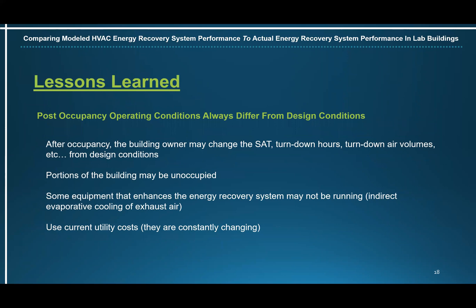Post-occupancy operating conditions always differ from design conditions. After occupancy, the building owner may change the supply air temperature, turn-down hours, turn-down air volumes, etc. from design conditions. Portions of the building may be unoccupied. Some equipment that enhances the energy recovery system may not be running — for example, indirect evaporative cooling in the exhaust air. If this is designed into the system and shown in the model, and it's not running for the first year or so, it has a tremendous effect on the cooling recovery.